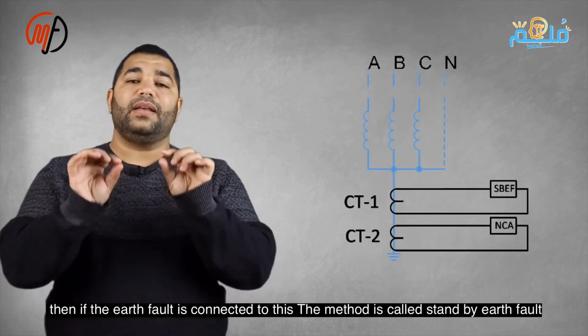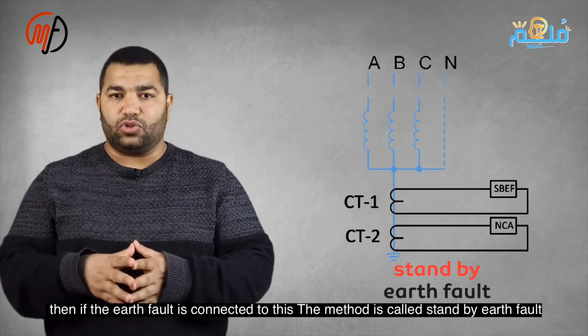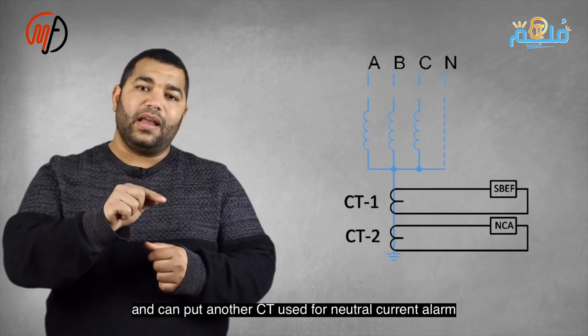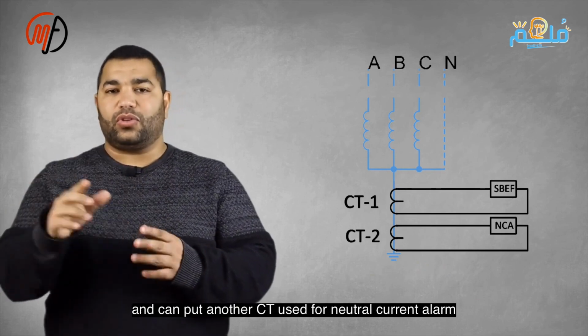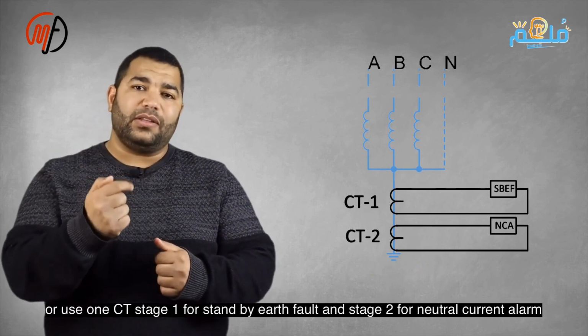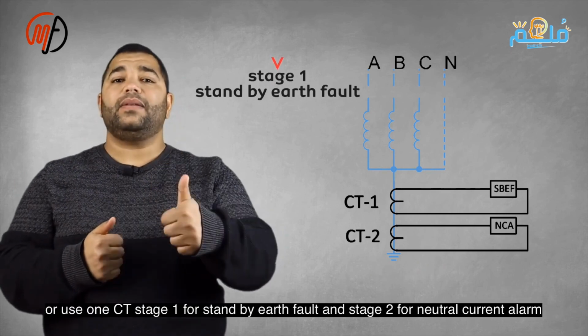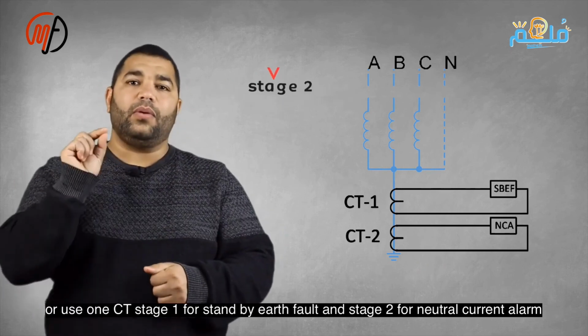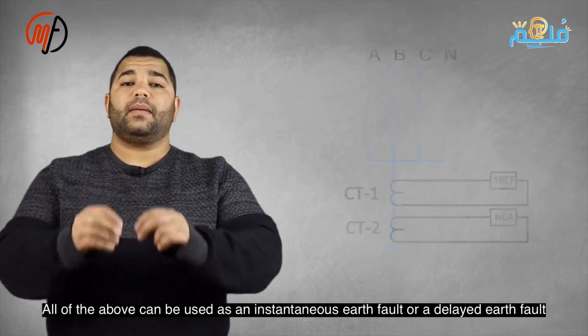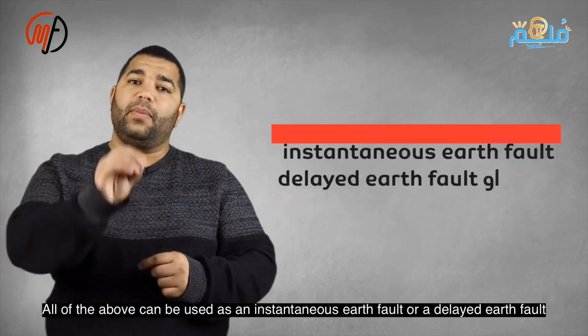You can place another CT for the neutral current alarm, or use one CT with stage 1 for the standby earth fault and stage 2 for the neutral current alarm. Everything mentioned can be used as either an instantaneous earth fault or a delayed earth fault.